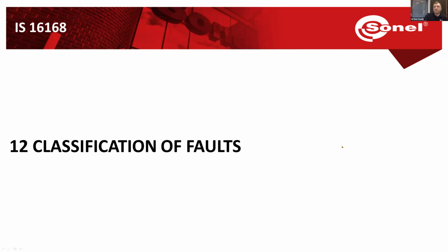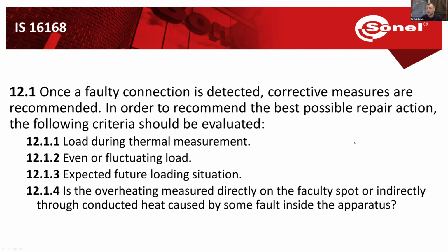Now that we've found some anomalies, how do we classify the faults? First, when we find a faulty connection, we need to take corrective measures, and there are criteria to evaluate. First is the load: is it present during measurement, is it even or fluctuating, and what's the expected loading situation in the future? Also, we need to check whether the overheating is measured directly on the component we want to check, or whether it's conducted through other parts—for example, we see the cover of a component, but something inside is causing the heat.